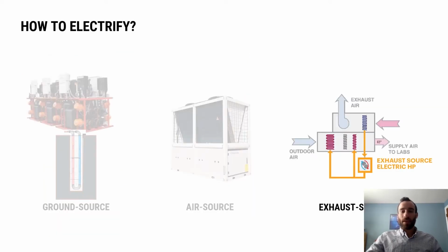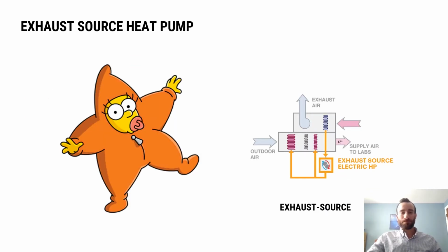So the last type of heat pump I want to go through real quickly is called exhaust source heat pumps. The fundamental principle of an exhaust source heat pump is that if we have a building with a good envelope, really the only remaining requirement for heating is the ventilation system. So if we can neutralize the impact of the ventilation system by recovering as much heat as possible from the exhaust airstream and use that as a source of heat for the building, we've essentially wrapped our whole building in a really warm blanket, and all the heat that we need to keep that building running can come from the internal gains inside, from the people, the lighting, and the equipment.